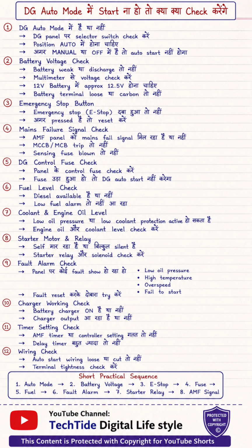Next, check whether the battery charger is working. Make sure the charger is on and charging output is available. Now check the timer settings. AMF timer or controller settings should not be incorrect. Also make sure the delay timer is not set too high. Finally, check the wiring. Auto start wiring should not be loose or cut. Also check all terminal tightness properly.